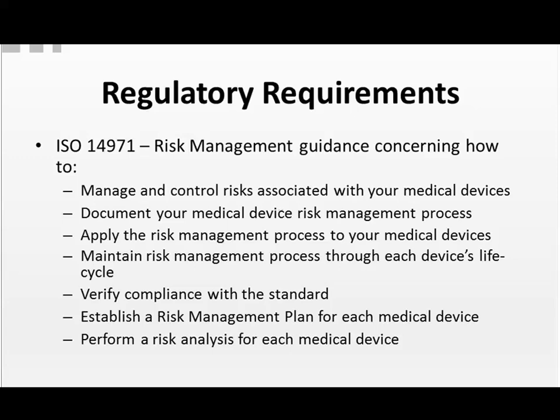In determining to use ISO 14971, there may be additional ongoing requirements to comply with, or to consider complying with, updated revisions. Now, the basic version is formally recognized by the United States Food and Drug Administration. As I said, it's 14971, the 2007 version, and it's recognized by the FDA as a consensus standard that can be used to support a pre-market application.